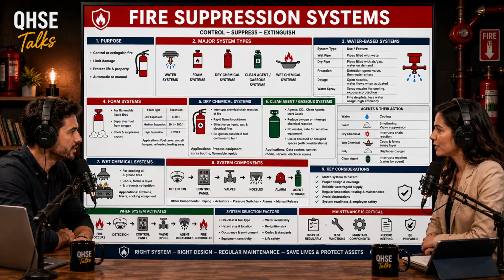Now, the final type of water system is the deluge system. And this one fundamentally breaks the rule we established earlier about individual sprinkler heads, right? It does. In a deluge system, all the sprinkler heads on the piping network are permanently open. They don't have glass bulbs, they're just open brass nozzles. So if they're open to the room, the pipes must be dry. Yes, completely empty. The system relies entirely on a separate, highly sensitive fire detection network, like UV flame detectors.